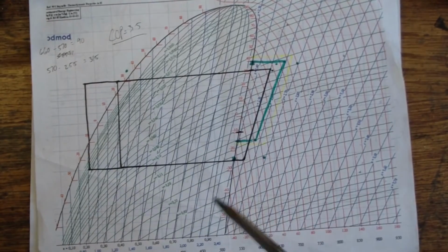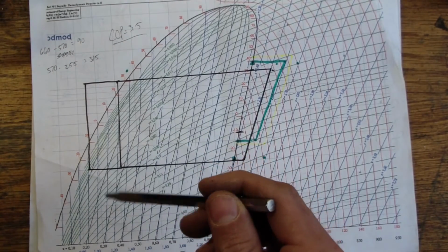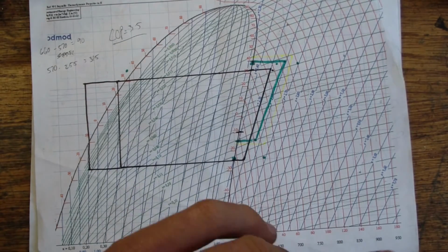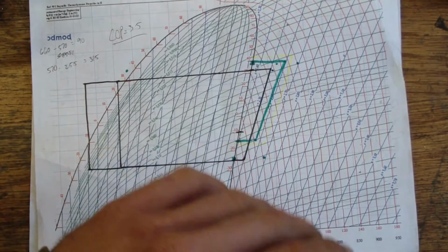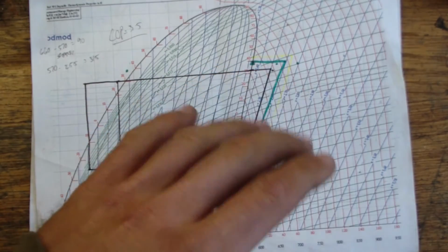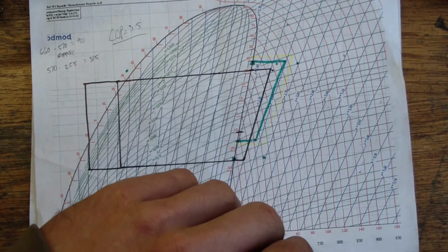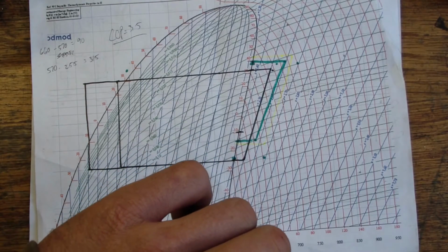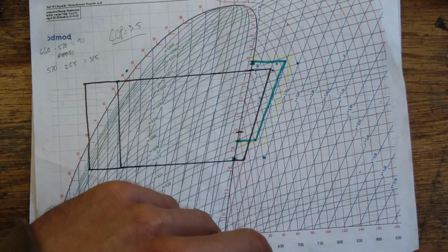What I think is another interesting aspect of these horns is they're a little better for refrigerant selection. Okay, why? Well, because if you look at a couple different refrigerants, I'm sure you've noticed by now that they all have different pressure temperature relationships, and they all have different boiling points at atmospheric pressure. Some of them are much lower, some of them are much higher. Methane is extremely low, like negative 200 and some odd degrees Fahrenheit, very, very cold. Whereas something like isobutane is at like 12 degrees Fahrenheit, and butane itself is like 30 or 31 degrees Fahrenheit.